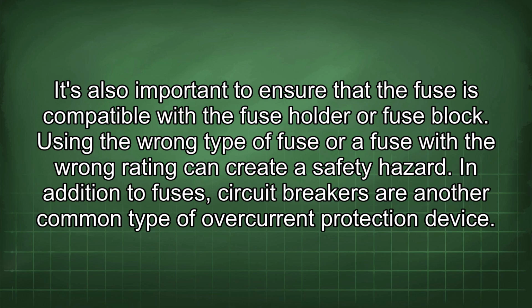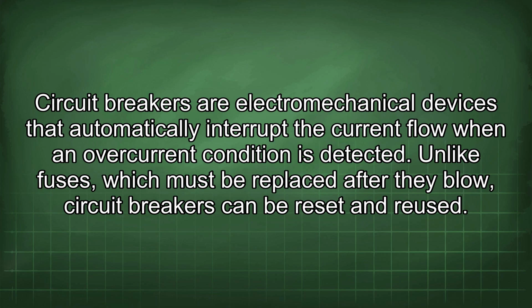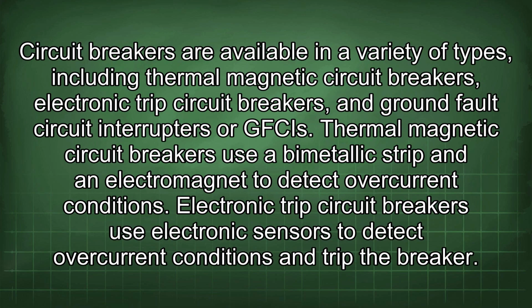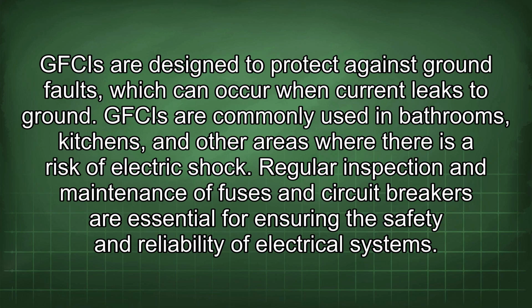In addition to fuses, circuit breakers are another common type of overcurrent protection device. Circuit breakers are electromechanical devices that automatically interrupt the current flow when an overcurrent condition is detected. Unlike fuses, which must be replaced after they blow, circuit breakers can be reset and reused. Circuit breakers are available in a variety of types, including thermal magnetic circuit breakers, electronic trip circuit breakers, and ground fault circuit interrupters or GFCIs. Thermomagnetic circuit breakers use a bimetallic strip and an electromagnet to detect overcurrent conditions. Electronic trip circuit breakers use electronic sensors to detect overcurrent conditions and trip the breaker. GFCIs are designed to protect against ground faults, which can occur when current leaks to ground. GFCIs are commonly used in bathrooms, kitchens, and other areas where there is a risk of electric shock.